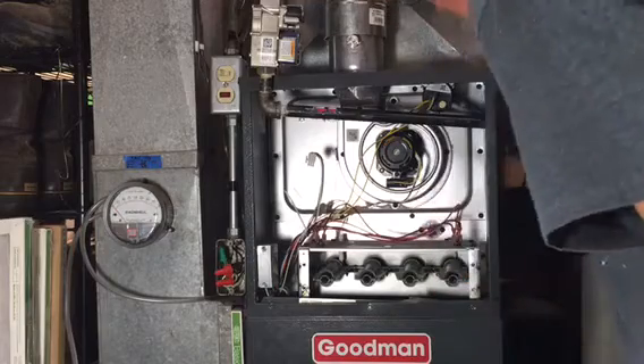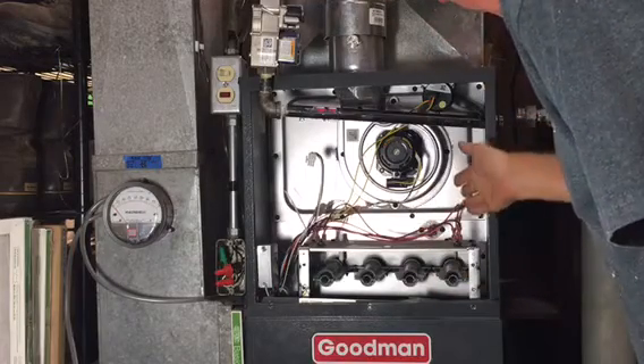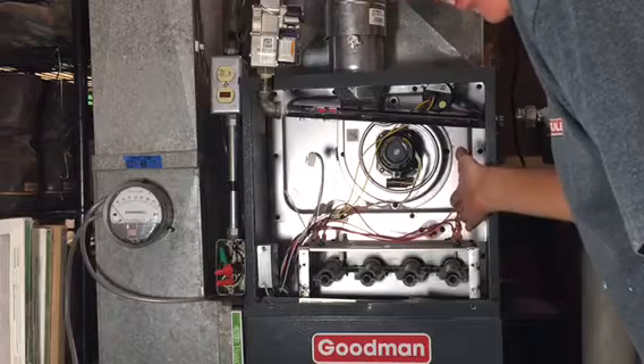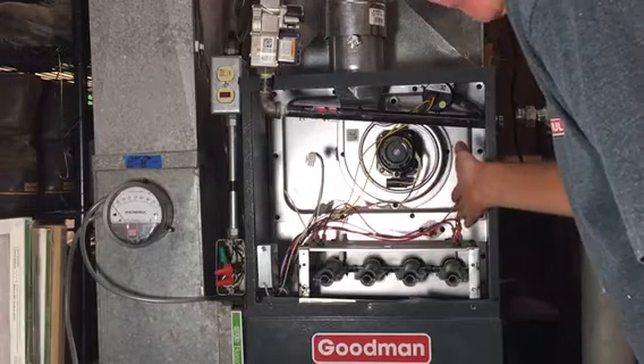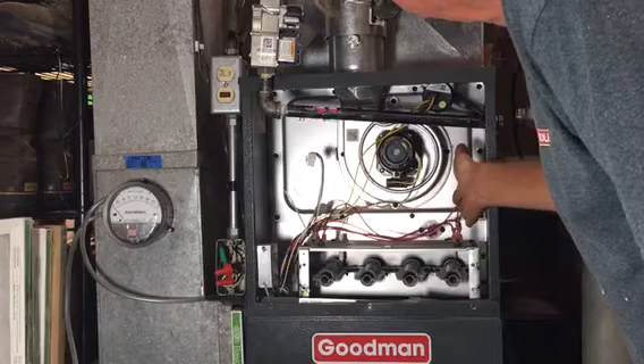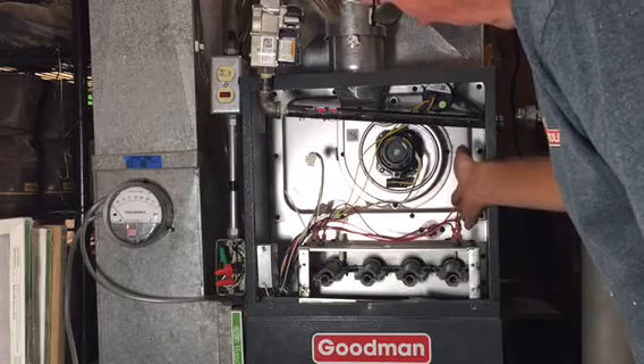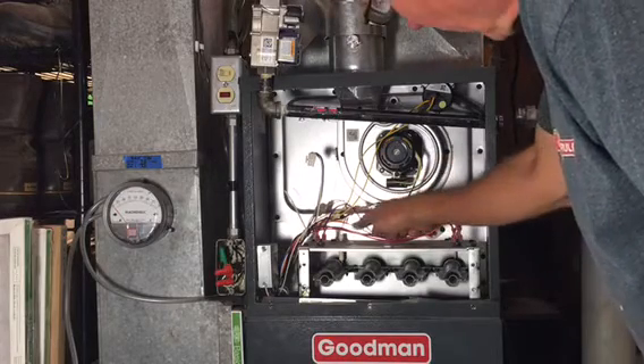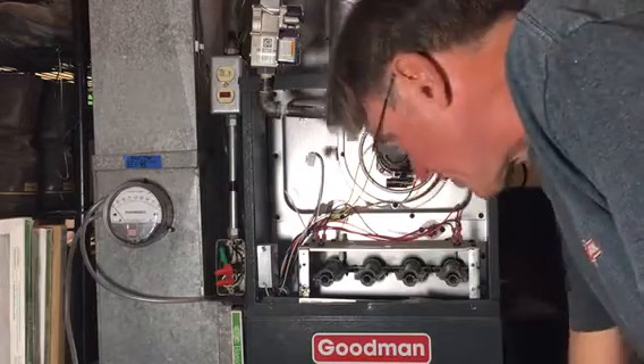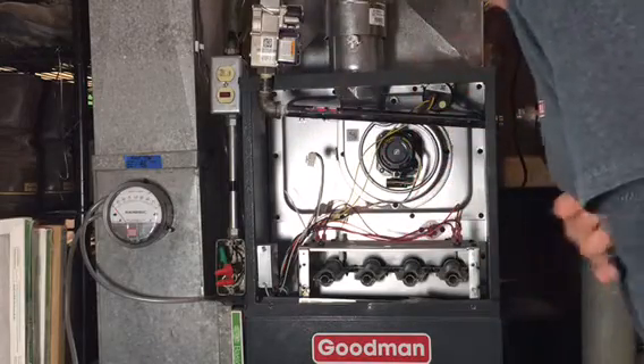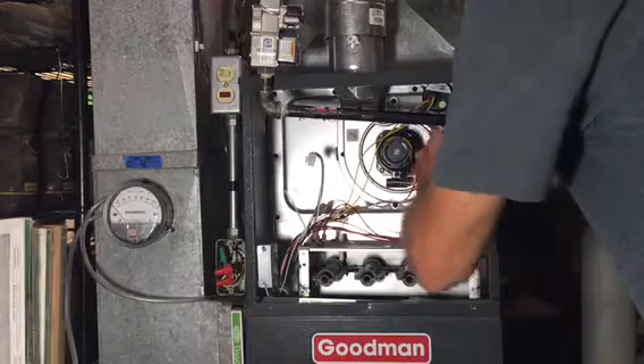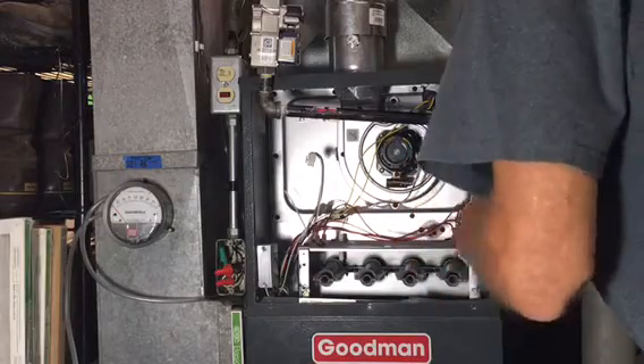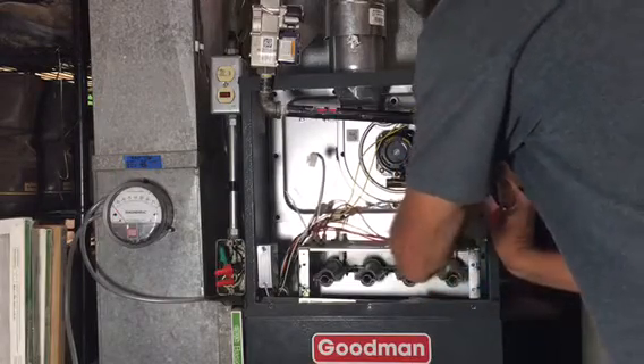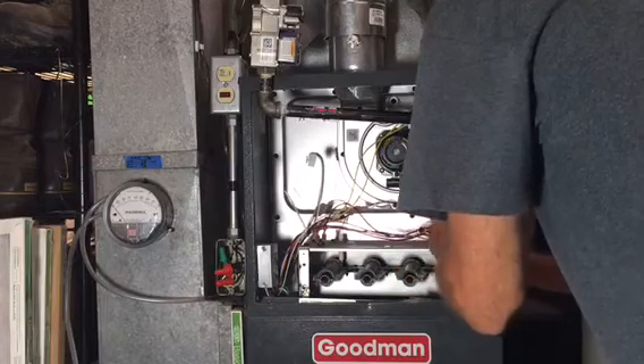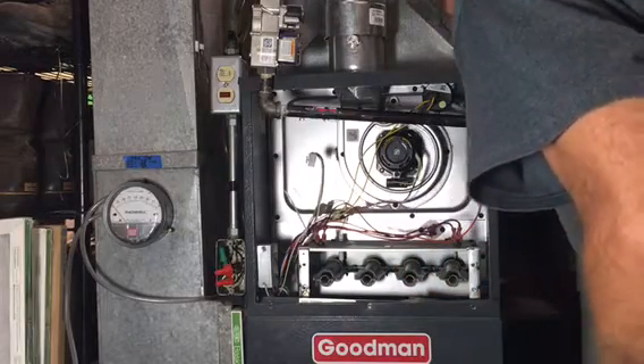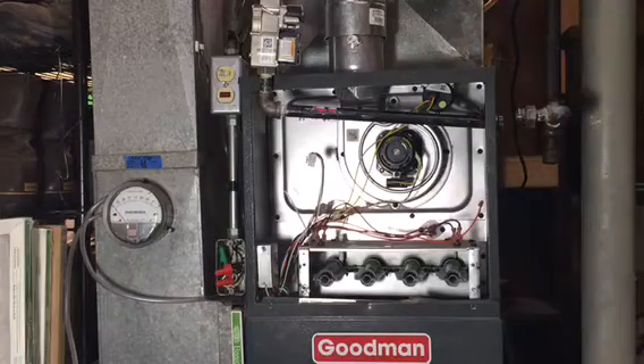First, we'll take out a couple important pieces. Over here is the flame sensor. It doesn't allow the gas valve to come on, or remain on rather, unless it senses a flame when it fires. And also here is the electronic ignition, both of which are kind of sensitive, so we don't want to get those banged around. Usually safer to take those out. And there's just a little screw on each of those. I'll disconnect the wire, and there's ways we'll test that I'll measure earlier. So let's get those out of the way.